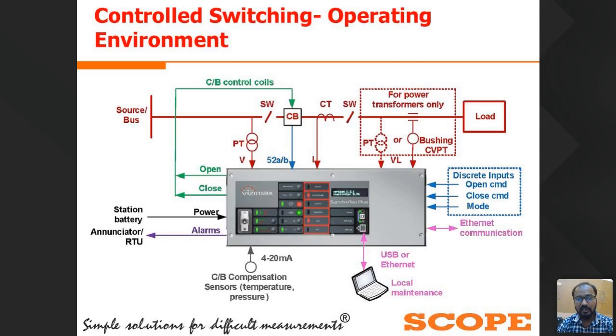So whenever the CSD receives a command from the TNC switch or from the SCADA system, it will hold the command and synchronize the breaker operating time with the system voltage or current, and then execute the command to the circuit breaker, so that the circuit breaker can operate at the precise electrical moment whenever we want to operate it. So we can also provide the alarms to the annunciator circuit through the control switching device. Basically these are the inputs and outputs of the control switching device.